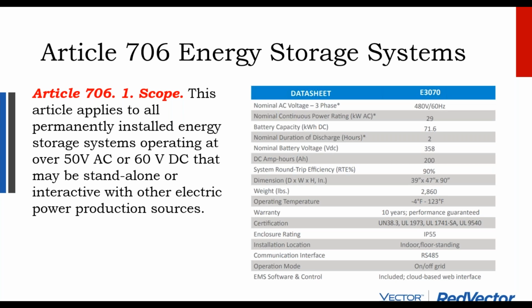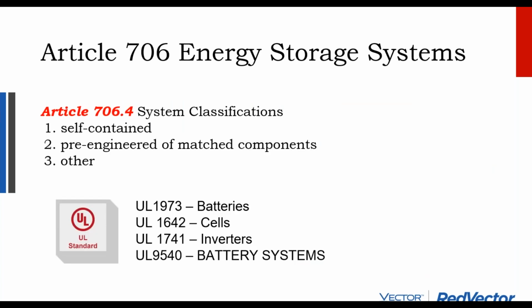And what I want to point out is that 706 only applies to circuits that are over 60 volts DC. So these requirements do not apply to 48 volt nominal battery banks. But you shouldn't ignore the logic behind these Section 706 requirements. This is where you get into requirements for overcurrent protection in the battery lines, and more robust requirements. And this is what we'll see in the future as we get into high voltage systems.